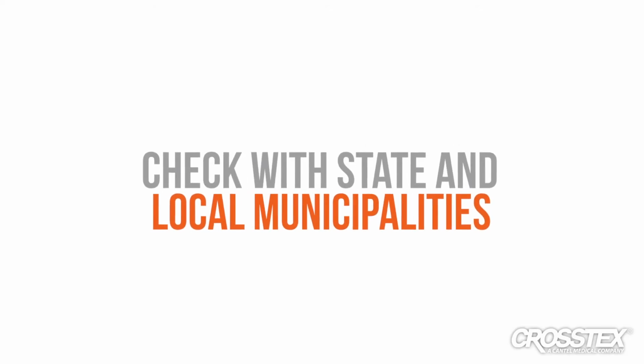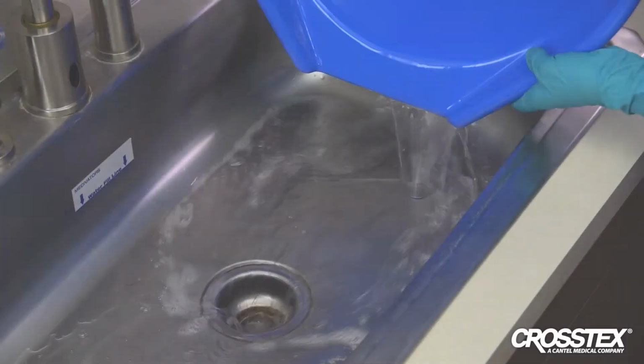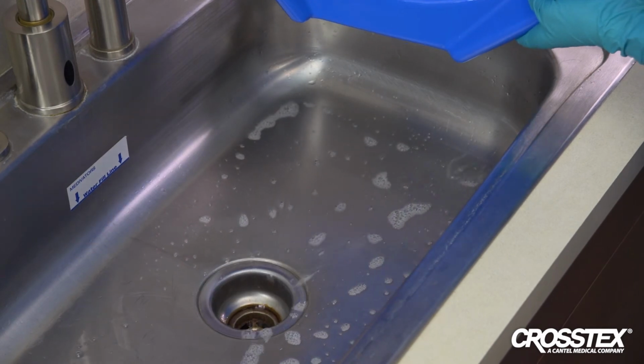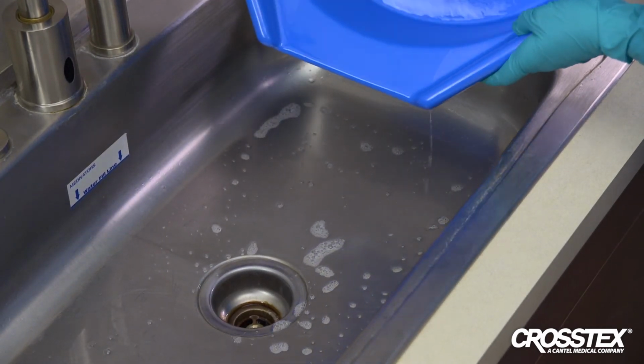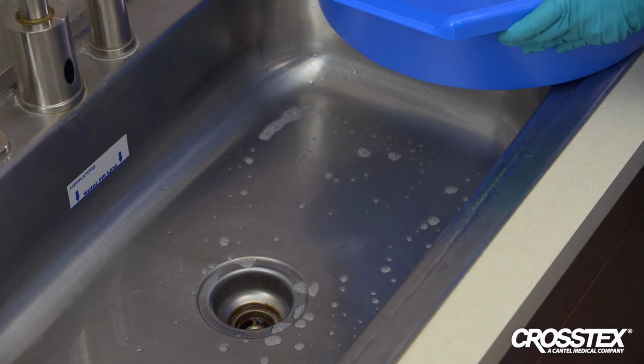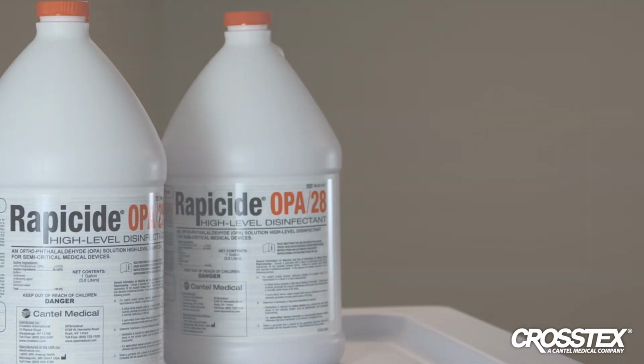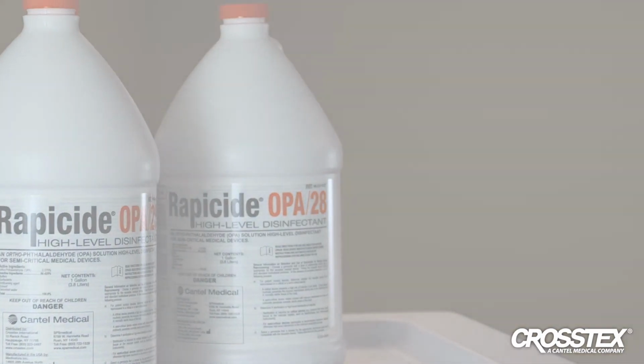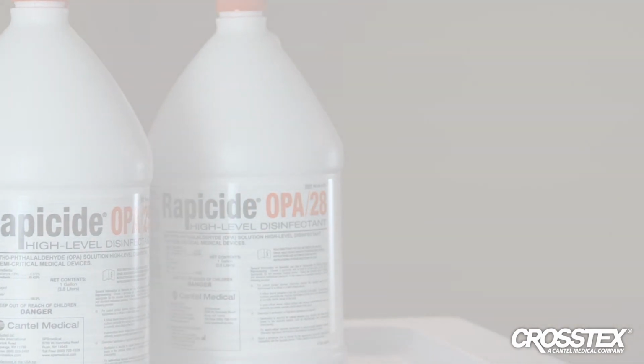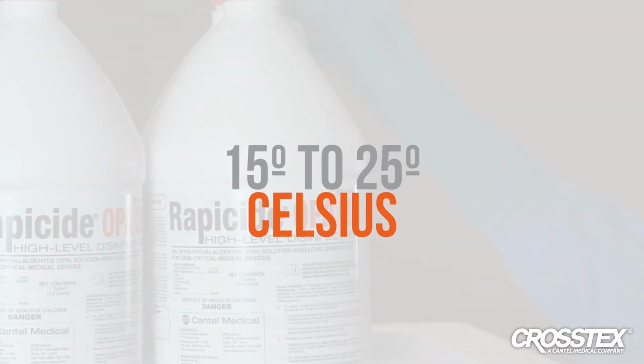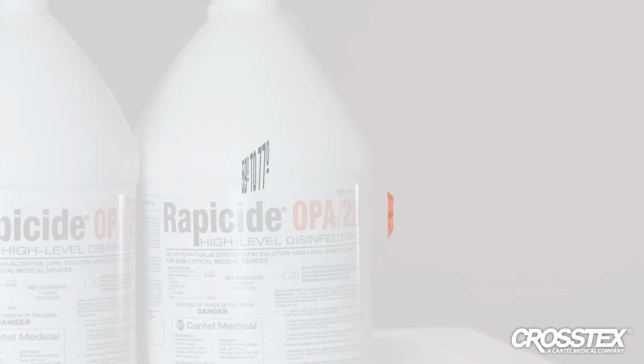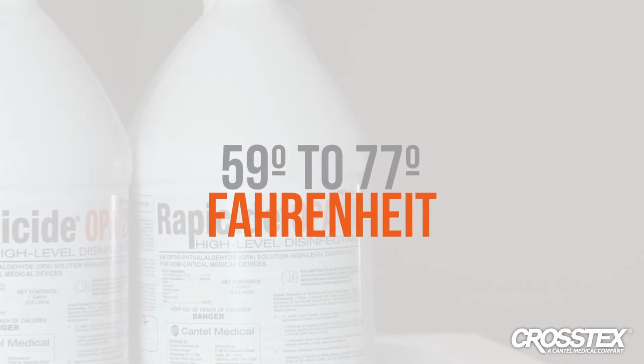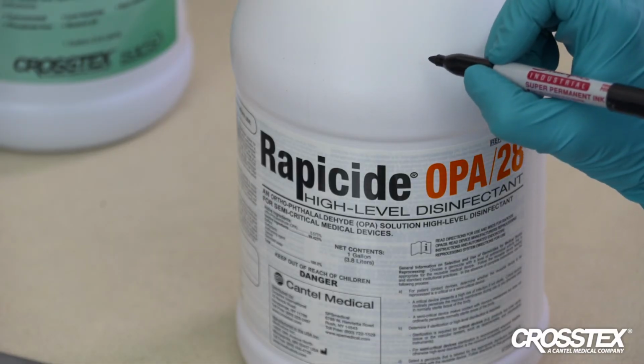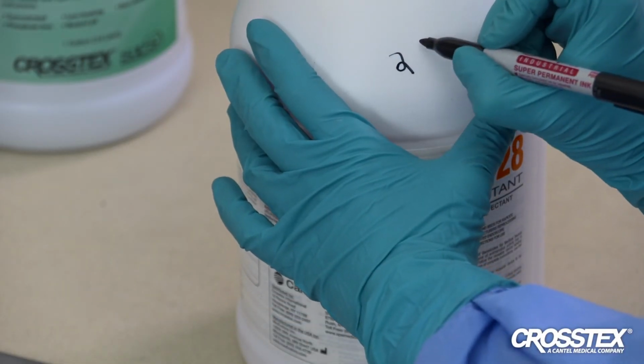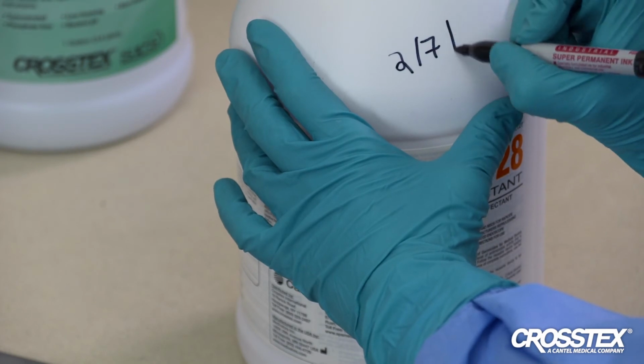Be sure to follow any state, local, or department disposal regulations when disposing Rapicide HLD, unless otherwise specified. Rapicide OPA 28 HLD can be safely discarded down the drain, making sure to flush thoroughly with water. Store Rapicide OPA 28 in its original sealed container at a controlled room temperature of 15 degrees Celsius to 25 degrees Celsius, or 59 degrees Fahrenheit to 77 degrees Fahrenheit in a well-ventilated area. Once opened, the unused portion of the solution may be stored in its original container for up to 75 days until used.